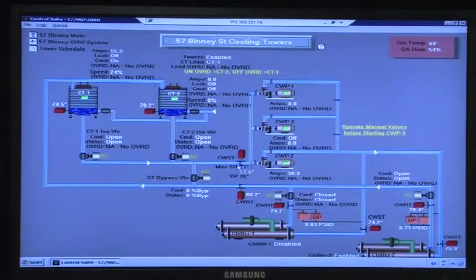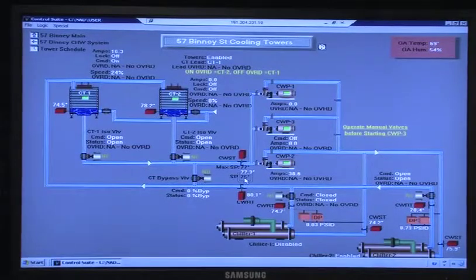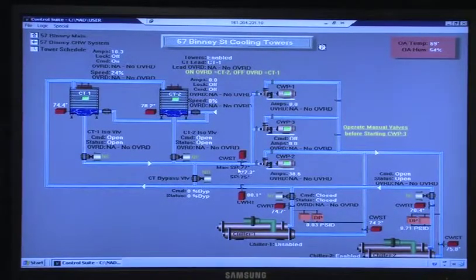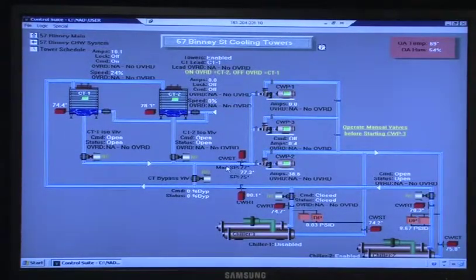Temperature continues to rise in the center of the tower. Is this here for that valve? This information? Yeah, 75 degrees. It's going to try to maintain 75-degree condenser water. If the water continues to rise, it's going to obviously divert the water up to the tower. Tower's going to come on. It's going to try to maintain that max set point of 77. So the tower fans are going to stage on, and then the speed of that fan is going to go up and down off the temperature to control for that set point.